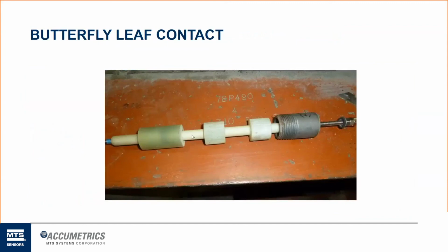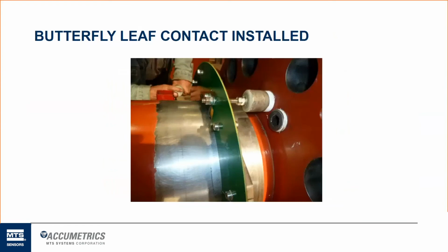We then cover our stainless steel threaded rod in this fiberglass material to prevent any risk of voltage breakover to the coupling flange bore itself, which would obviously be field ground, or the metal steel of the machine. These pieces offer strength and will be a tight fit inside that bore to prevent any bending or warping of our threaded rod. The more narrow pieces are just covering it to prevent voltage breakover. Then it gets threaded in with this pipe thread piece on the end. That shows an example of how we install that into the coupling flange. Again, this is for the larger, typically hydrogen cooled Westinghouse machines, and is how we do the connection for the negative and positive side of the field.